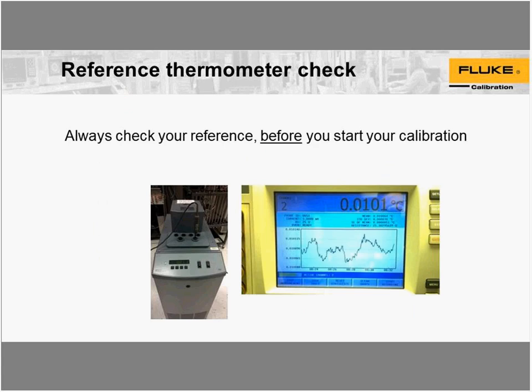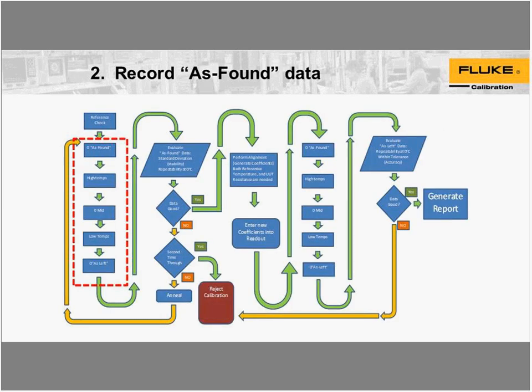Here, you can see what I'm doing is I've got my SPRT in a full-size RTPW cell. It's in a 7312 maintenance bath. And I've got a picture also of the 1595A readout display. As you can see right now, I am reading 0.0101 degrees Celsius, and where we want to be is 0.010. I think 1/10,000th of a degree is probably acceptable. Right. The next step is we're going to record our as-found data.